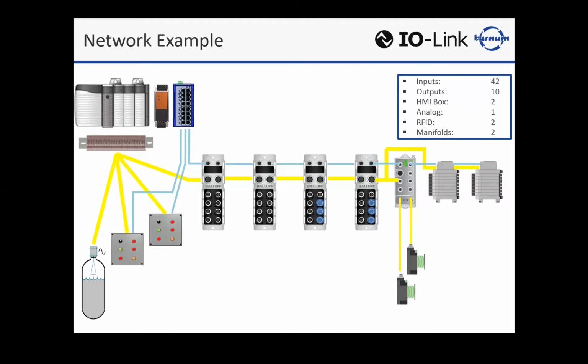So you can see in this model, we've cleaned things up a bit because we have very few connections back to the panel. We can decentralize now and put our hardware components where we need them in the field, meaning we're not as limited in flexibility of where we can mount these, or concerned about hardwiring them all the way back to a main panel. We can be very flexible because we're using connectivity now between point A and point B. And by switching from parallel to network, if you needed to add more IO, you would have to add another one of these IO blocks, valve manifolds, et cetera.